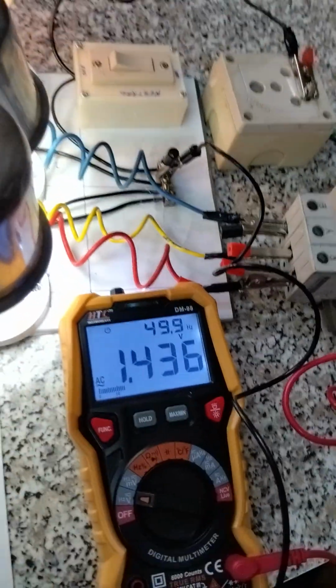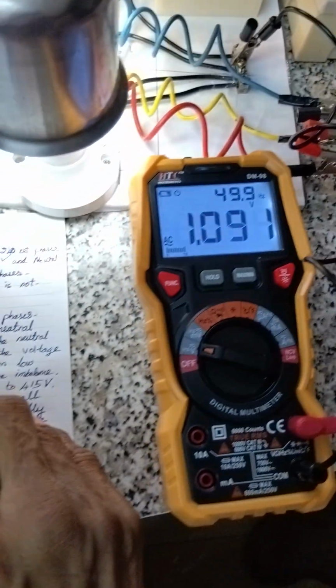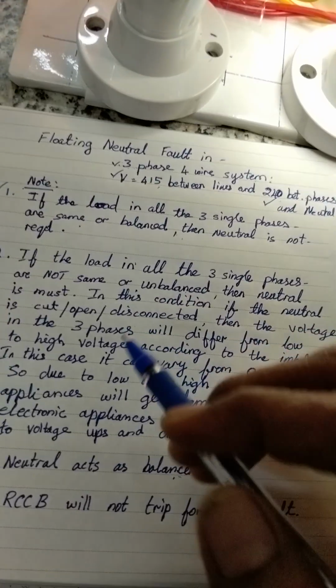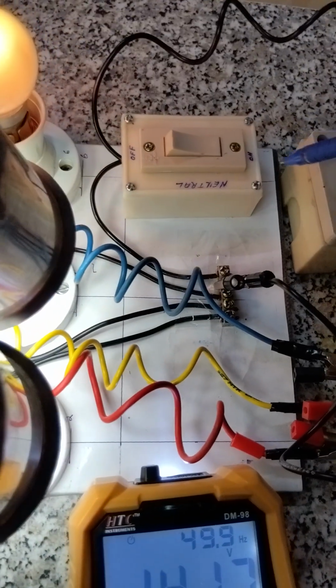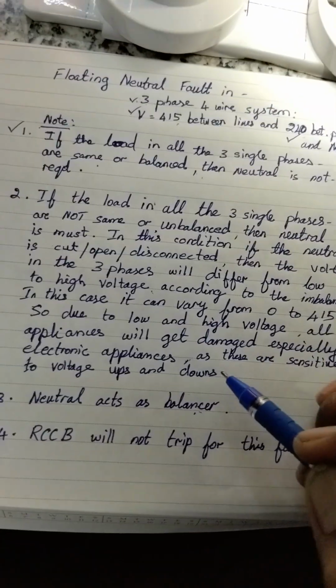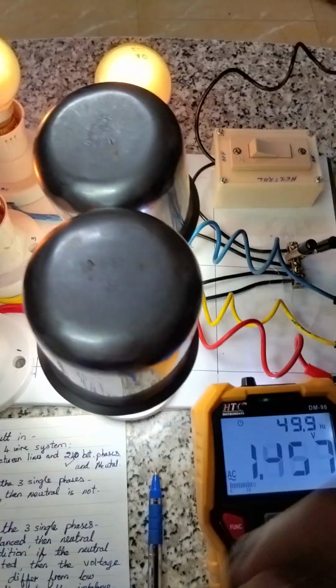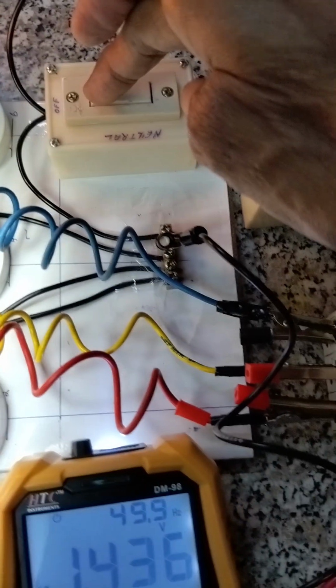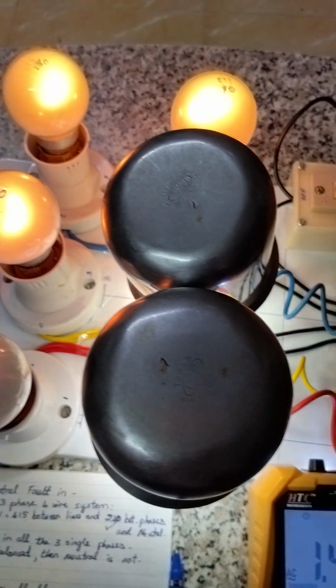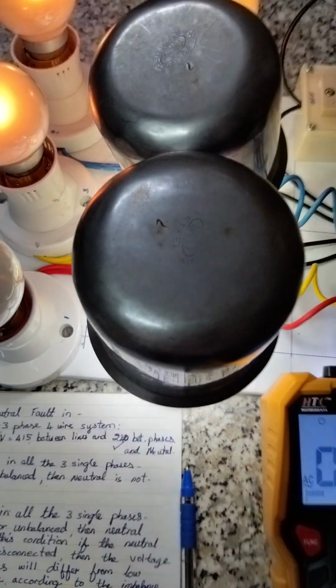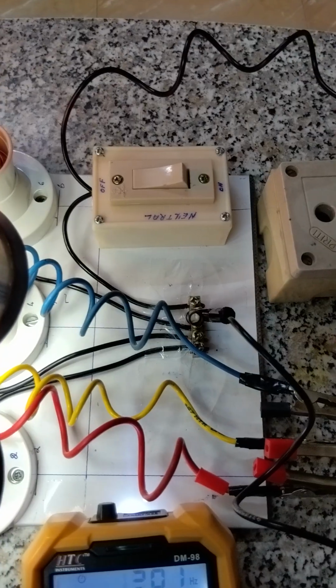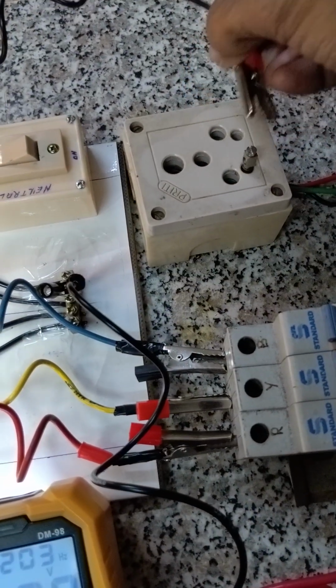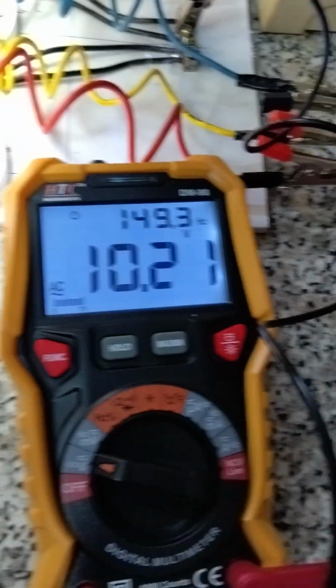Now what I will do, we have to prove the second point. First, with the voltage between phase and neutral, with the neutral on. Now we have to disconnect the neutral and see what is happening to the voltage. Now I am disconnecting the neutral. I have disconnected the neutral. For clarity, I will remove this also. Now there's no neutral. Now we will check the voltages between each phase and neutral.